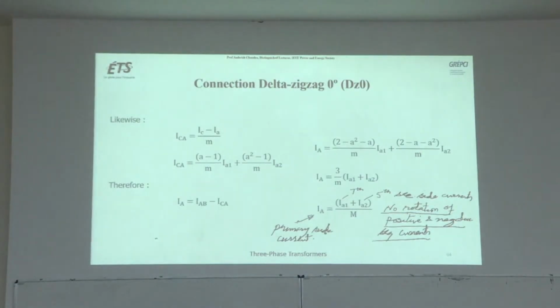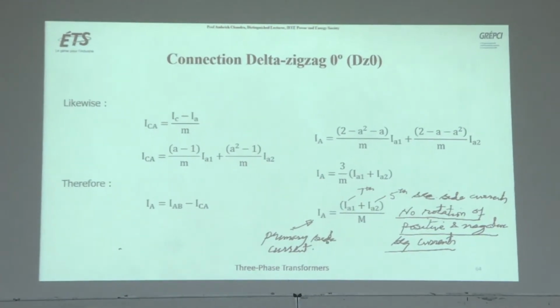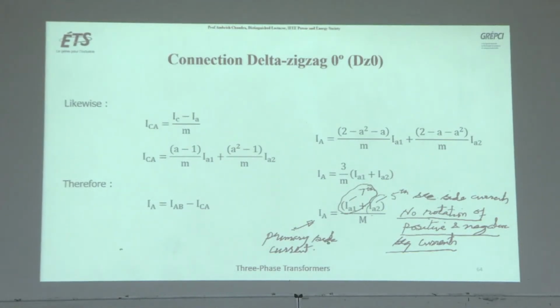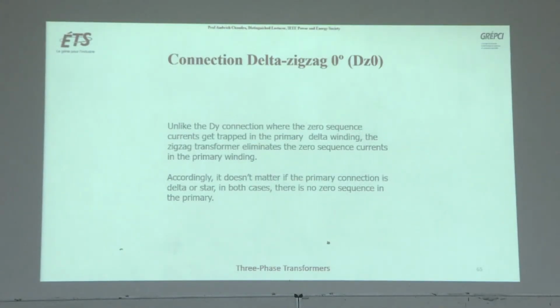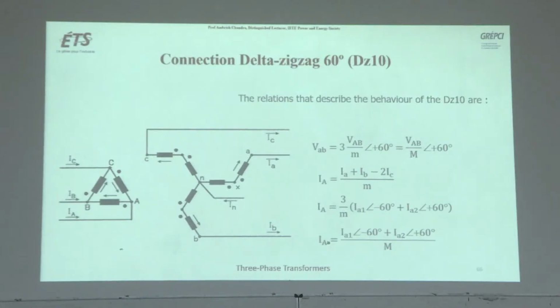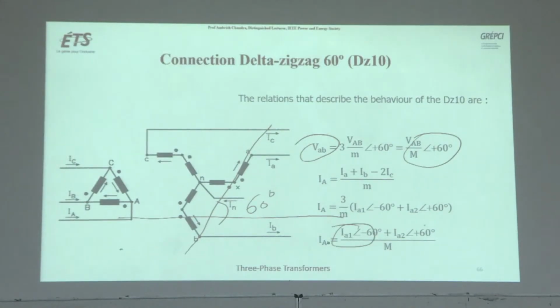I will not go into much detail of this, although I have put it in the notes. So you see, 7th harmonic, and this is the 5th harmonic, no rotation of positive or negative sequence harmonics. This is DZ10, so there is a 60-degree phase shift between the secondary voltage and the primary voltage. That is, the secondary voltage is leading by 60 degrees to the primary voltage. And then you can see the rotation of positive sequence and negative sequence.